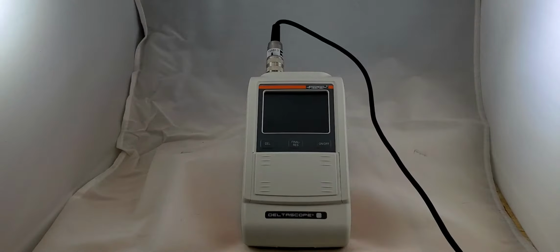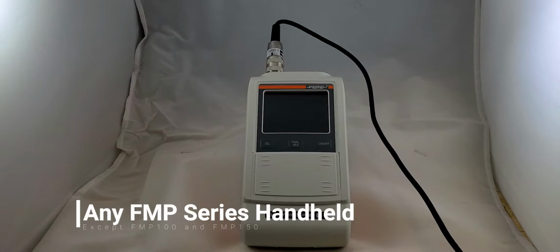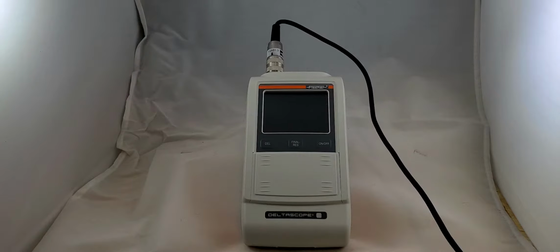Now this calibration is going to work for any of the Fischer FMP series except for the FMP 100 and 150. So if you have a Deltascope, a Dualscope, or an Isoscope that's not an FMP 100 or FMP 150, you're all set. Only difference is going to be when you have a 30, 40, or 50, you will have a couple different buttons, but the buttons that we need are all the same.